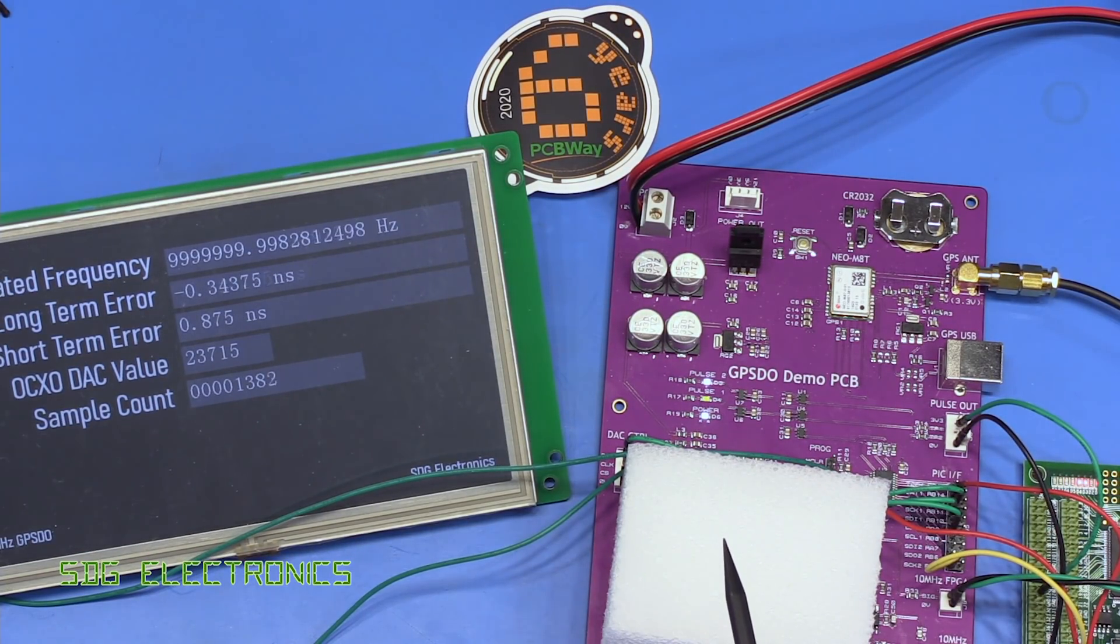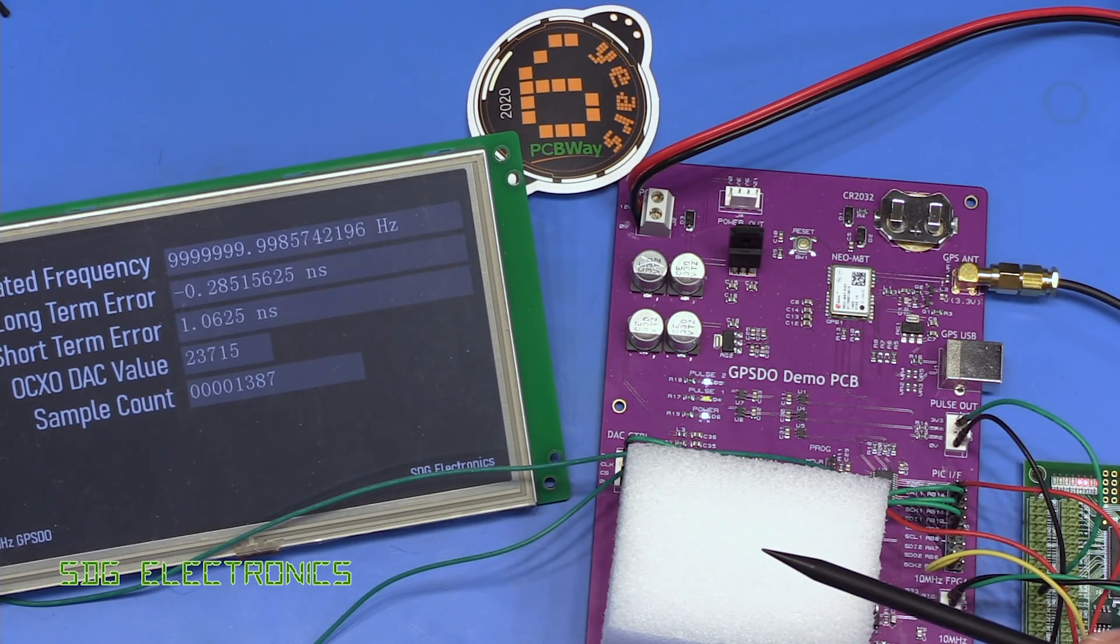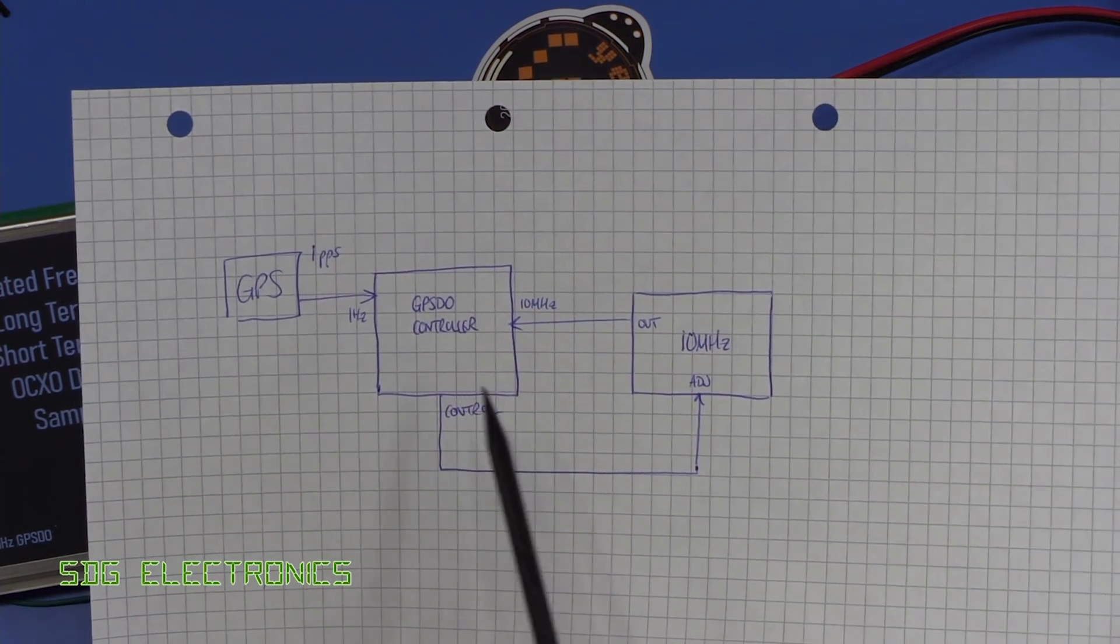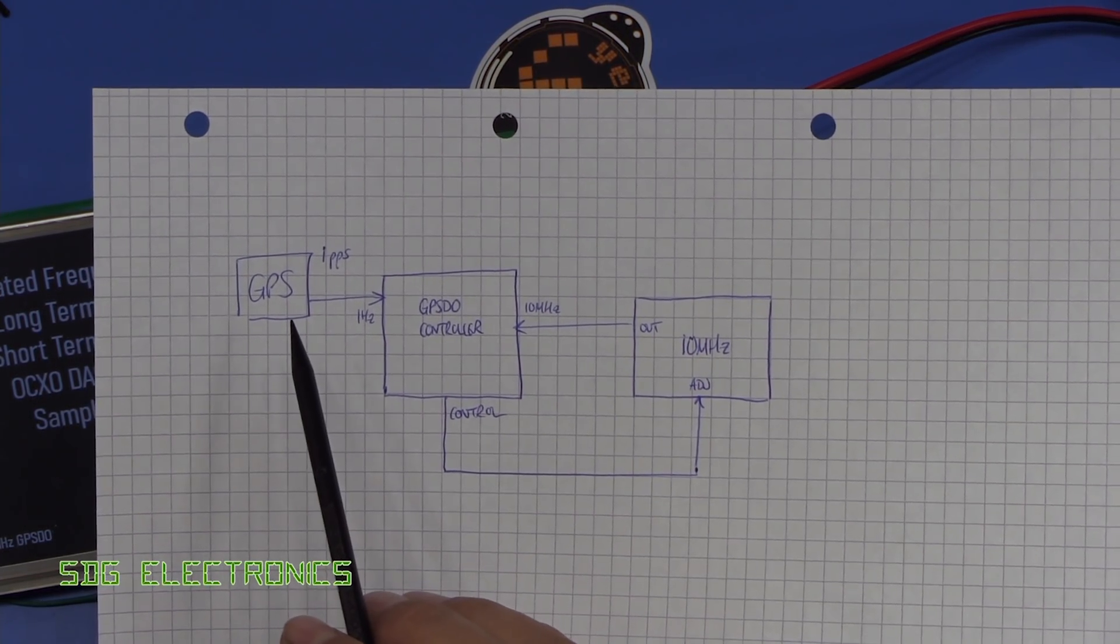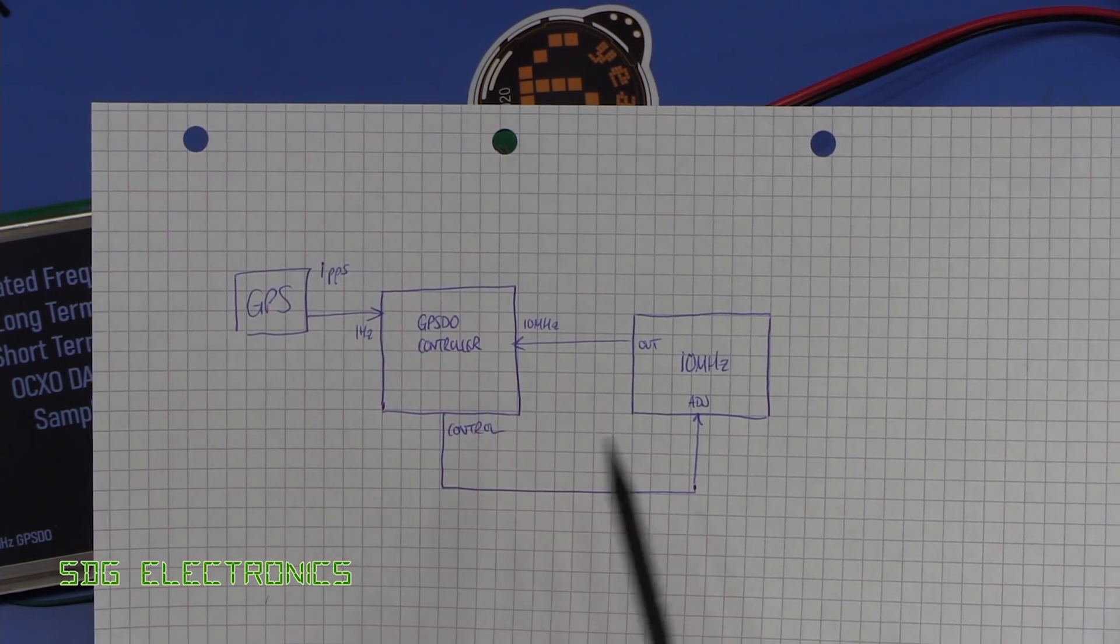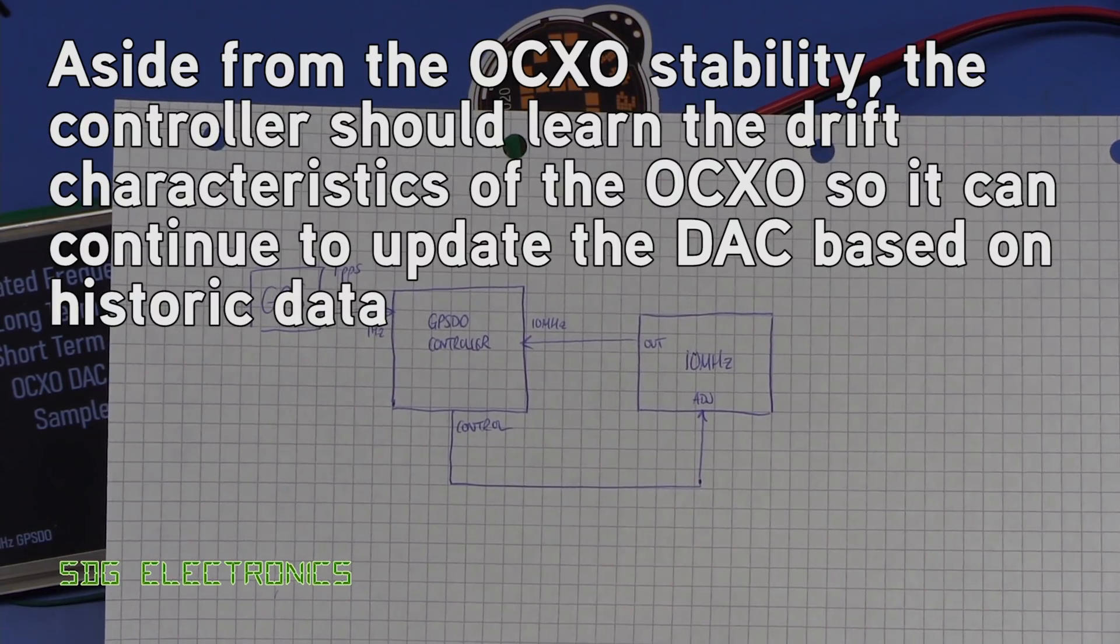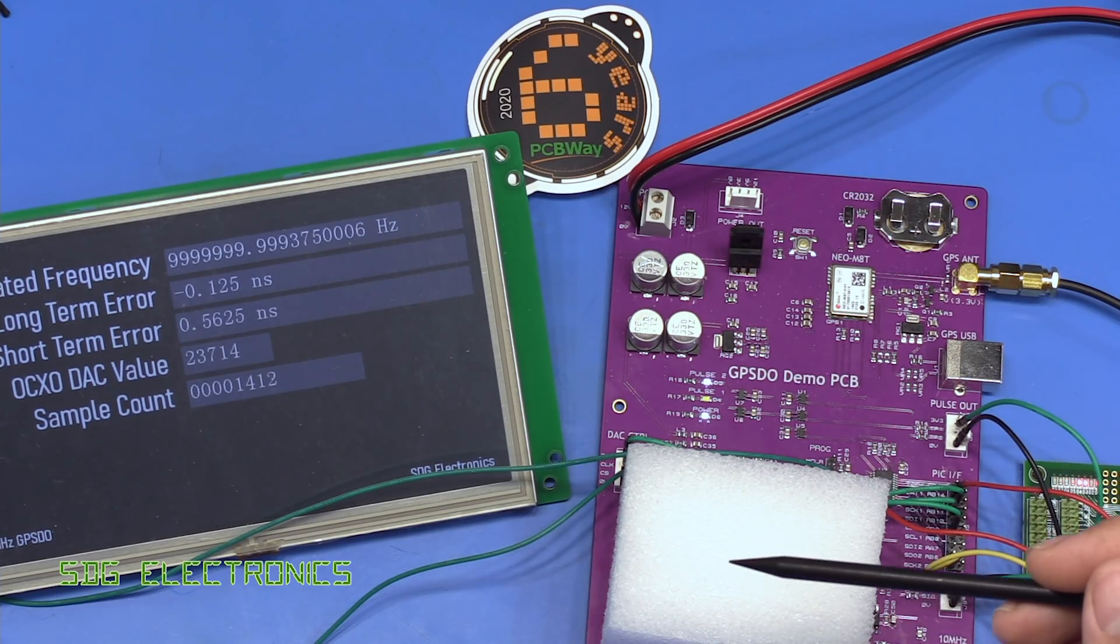This is a single oven oscillator, but what we really want is the most stable source possible. Because although this will work quite happily with even a basic crystal oscillator when we've got GPS signals, in the event of any loss of GPS or anything else, you want this system to be stable long term and at least give several days of holdover with very little drift.